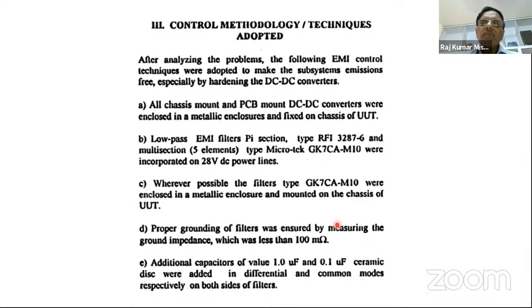Proper grounding of filters was ensured by measuring the ground impedance, which was less than 100 milliohm. There is a difference between earth and ground, so one should be absolutely clear about it. There should not be any doubt in that.